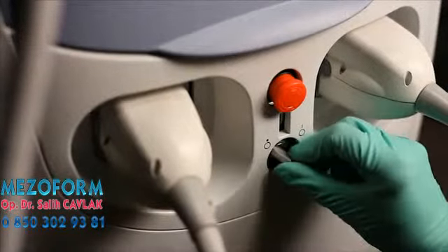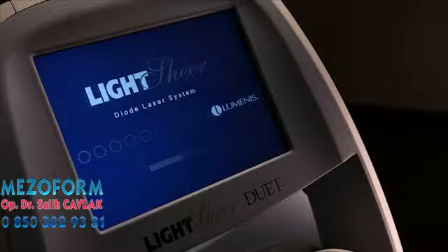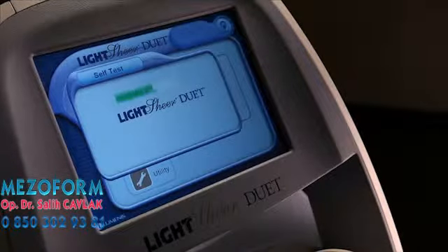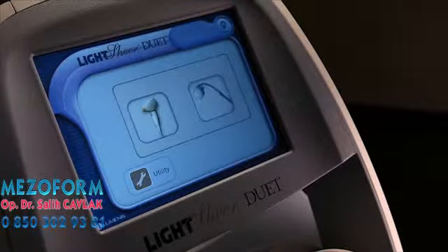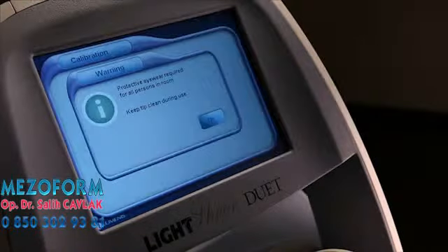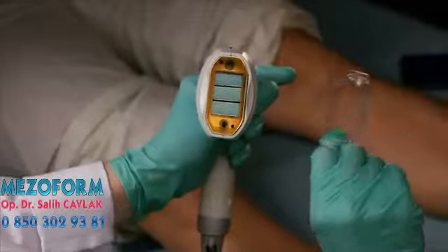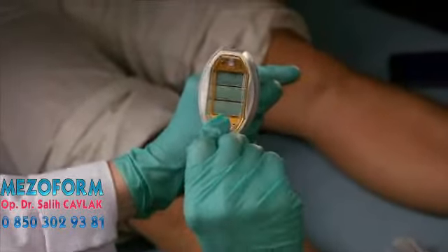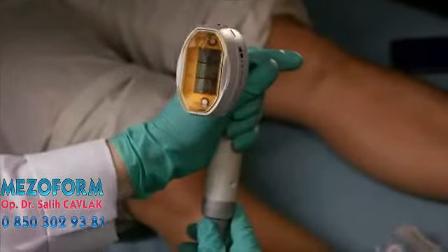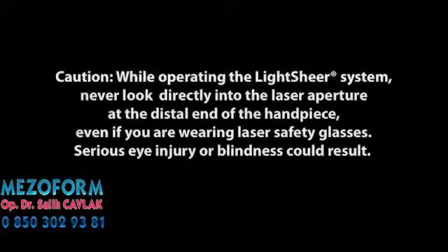Handpiece calibration is required upon system startup. Calibration is also recommended prior to each treatment. On the startup screen, select the handpiece that you intend to calibrate. Follow the steps indicated on the control screen. When calibrating the HS handpiece, ensure a clean disposable insert is attached to the handpiece. Caution: while operating the LightSheer system, never look directly into the laser aperture at the distal end of the handpiece, even if you are wearing laser safety glasses. Serious eye injury or blindness could result.